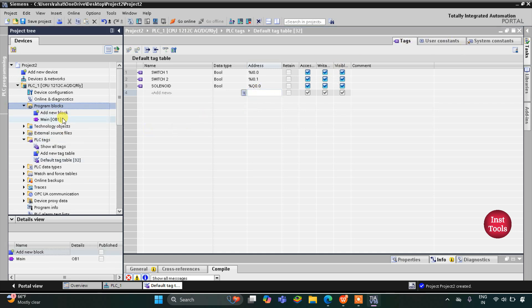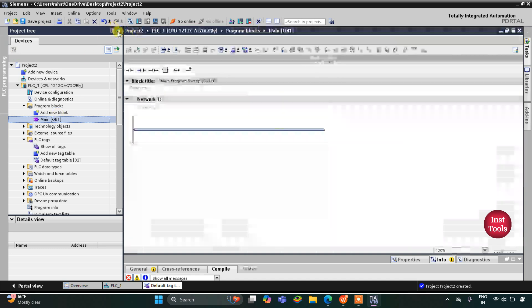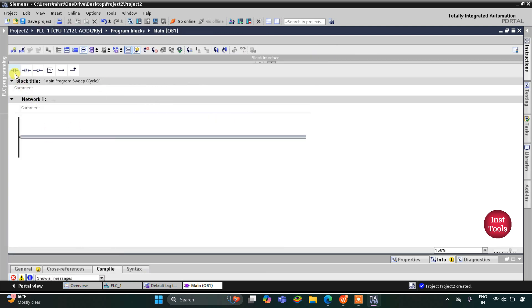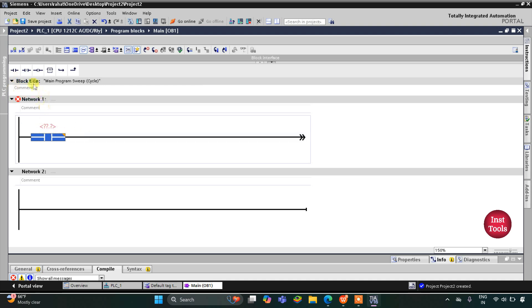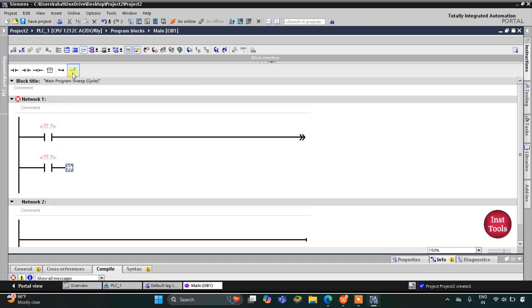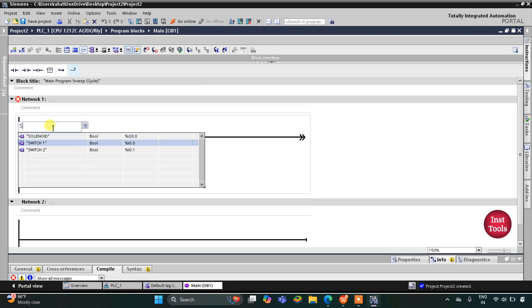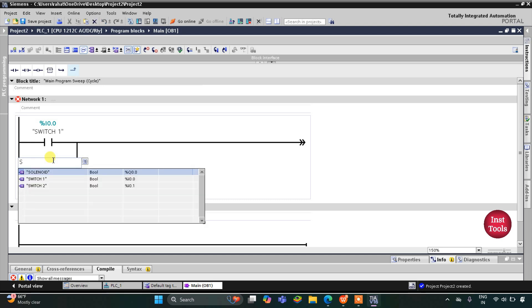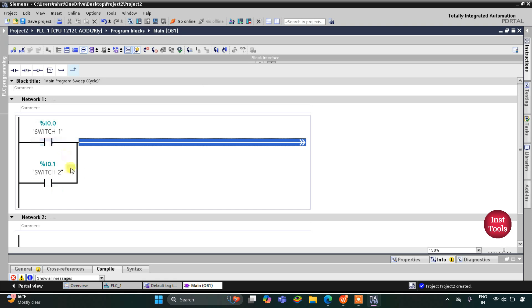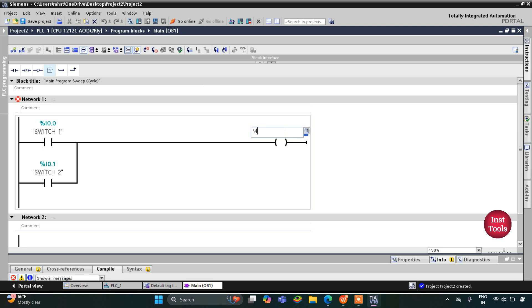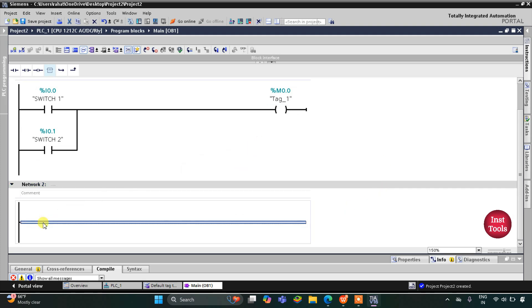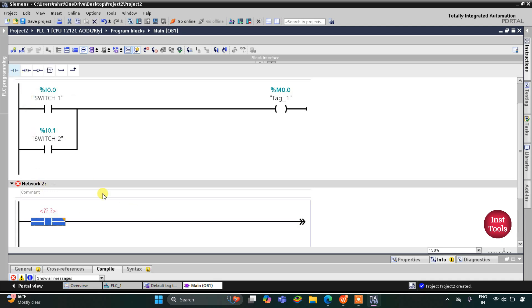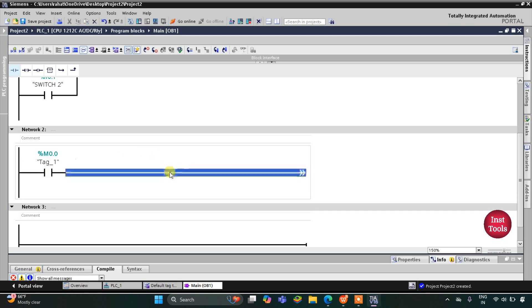I'll go to Program Blocks and then Main OB1 where we will draw the ladder diagram. I'll zoom in and insert a normally open contact for Switch 1, then open a branch and add a normally open contact for Switch 2, connecting them in parallel to implement the OR logic gate. This normally open contact is Switch 1 and this one is Switch 2. When one of the two switches is turned on, I'll insert a coil for memory bit M0.0. When M0.0 gets energized, the solenoid should turn on.